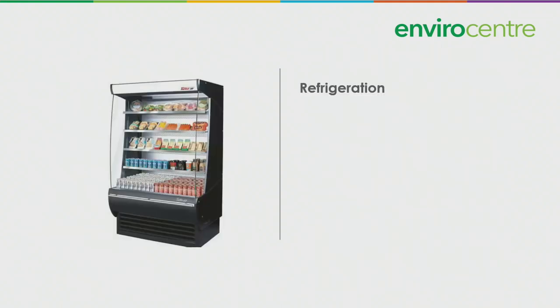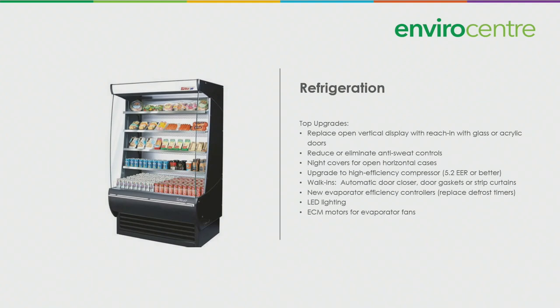Just looking at some of the other aspects of smaller businesses, often you have refrigeration. So the top upgrades are to replace your open vertical display, and that's what that is in the picture, with a reach-in with glass or acrylic doors. Reduce or eliminate anti-sweat controls, night covers for open horizontal cases, upgrades to high-efficiency compressors. If you have walk-ins, you can put in an automatic door closer, door gaskets, or strip curtains. New evaporator efficiency controllers. You can put in LED lighting and have ECM motors for your evaporator fans. Now, a lot of these things are actually eligible for rebates as well under the IESO program.